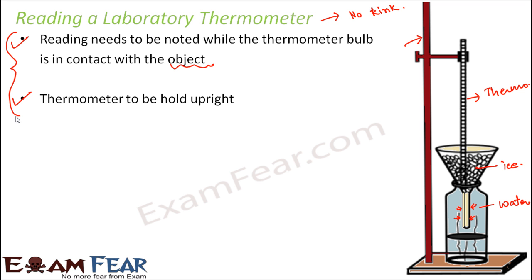Another important point: the bulb should never touch the surface of the container. If the bulb touches the container, the proper heating of the bulb gets disturbed. We want the bulb to be surrounded on all sides by the substance whose temperature needs to be measured — for example, when measuring the temperature of water, the bulb should be completely surrounded by water and must not touch the container walls.